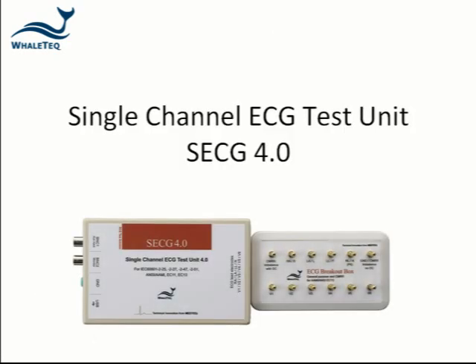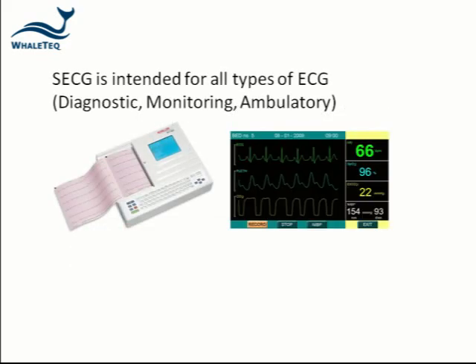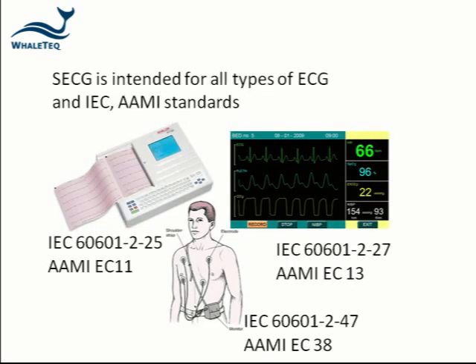The SECG, or single channel ECG test unit, is intended for all types of ECG equipment, such as diagnostic, monitoring and ambulatory, and all types of ECG standards such as those published by the IEC and AAMI.